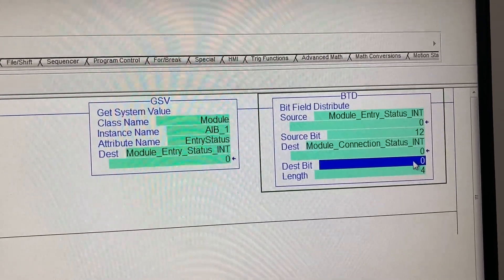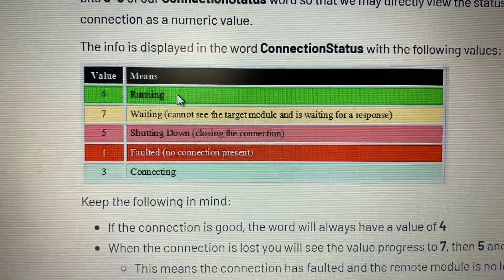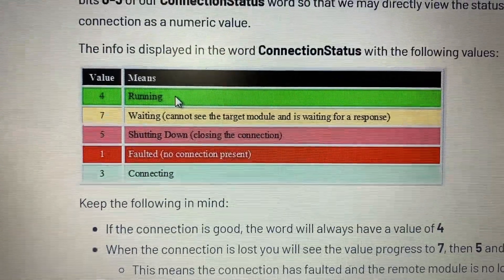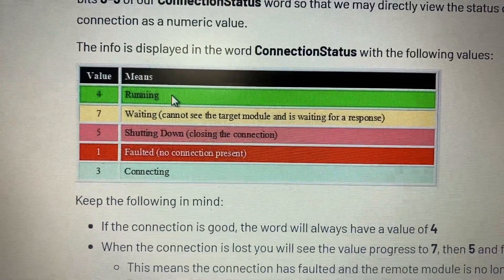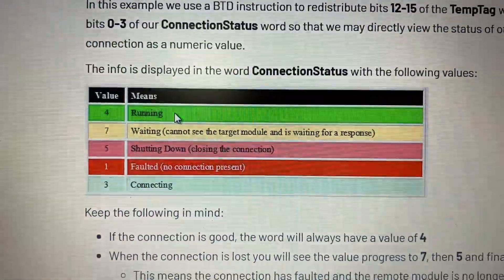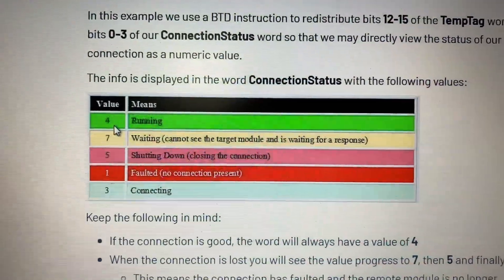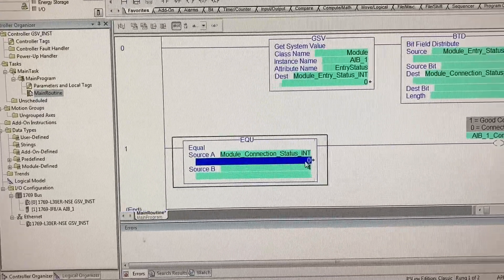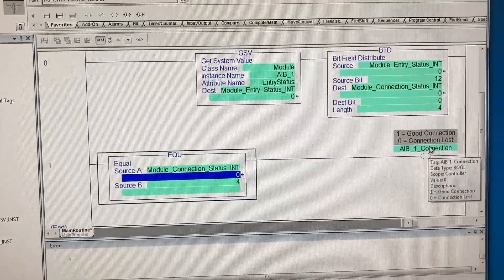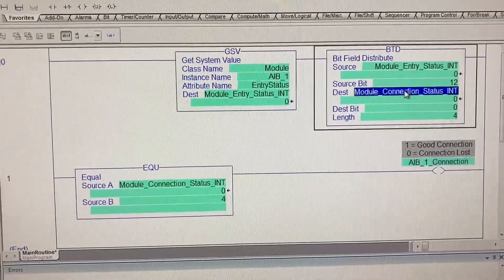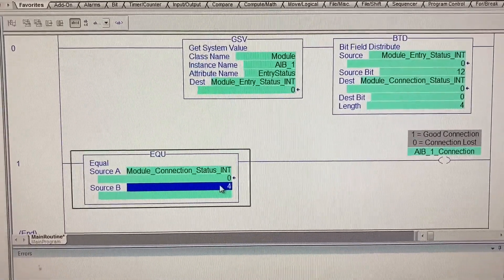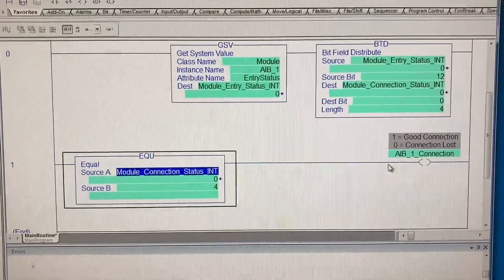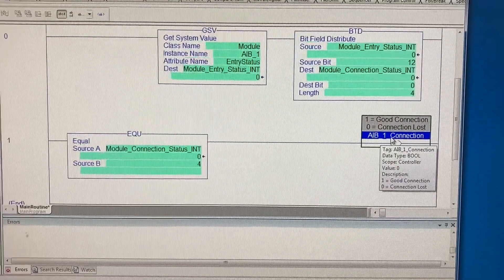This is the table from Rockwell Automation website. Basically if module connection status register value is 4, the connection is good. This is what's in the logic to check the connection for analog input module. If this is 4, connection is good, otherwise connection is lost.